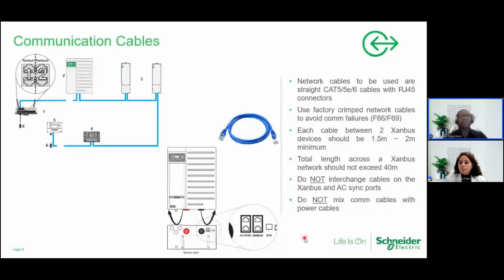One other thing is with your terminators, these little black things seen here. Some people see them in their devices and say, what am I doing with this, and throw it away. Keep those, they are very important. A terminator is basically a device used to show the system where you're starting and where you're stopping on your communication line, not on your AC synchronization line, because I've seen some people install terminators on the AC sync ports.